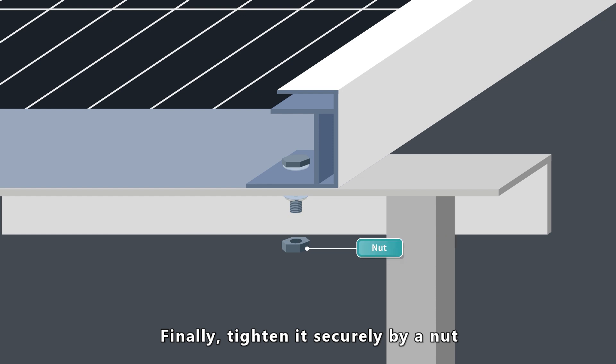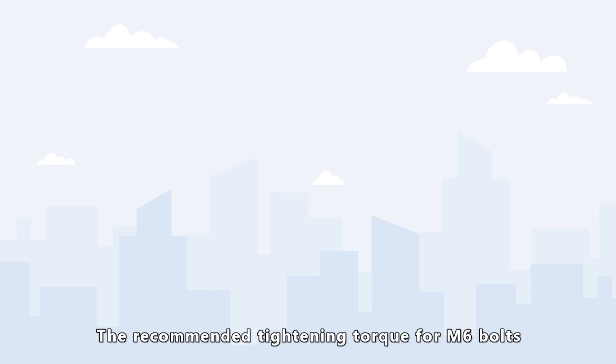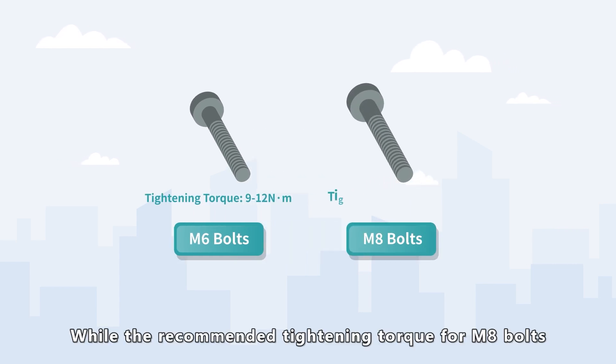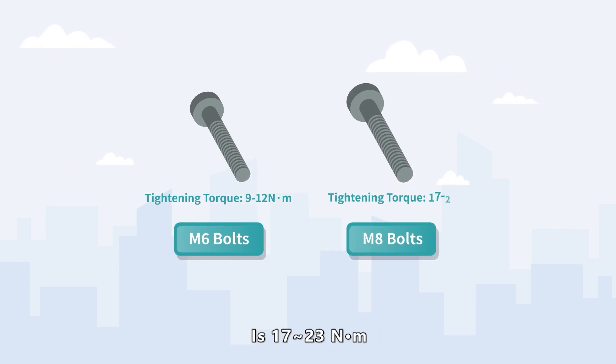Finally, tighten it securely by a nut. The recommended tightening torque for M6 bolts is 9 to 12 Nm, while the recommended tightening torque for M8 bolts is 17 to 23 Nm.